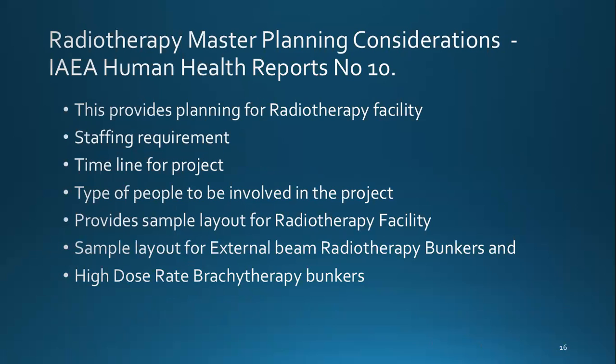This is a very small booklet, but provides significant information on planning a radiotherapy facility, staffing requirement, timeline for the project, type of people to be involved in the project, and provides a sample layout for the entire radiotherapy facility, including simulator, mold room, everything, where these should be located, etc. And sample layout for external beam radiotherapy bunkers, I will discuss this a little bit, and sample layout for HDR brachytherapy bunkers.